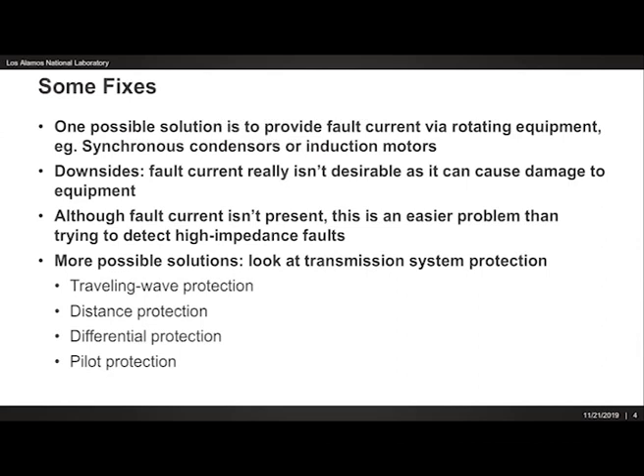However, this is a bit of a step backwards. One of the nice things about microgrids and inverter interface generation is they don't provide fault current. Fault current's dangerous. It can damage equipment. And we'd like to find a solution which takes advantage of the lack of it.